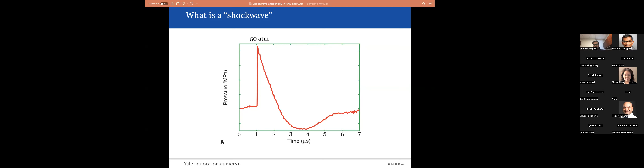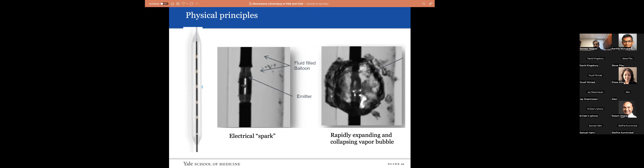So there's a transfer of electrical energy from a generator that's hooked up to the balloon catheter via an electrical cord, and that electrical spark ignites an emitter that is inside the fluid-filled balloon with 50-50 saline and contrast, and that induces the formation of a rapidly expanding and collapsing vapor bubble. And this initiates the transfer of an acoustic or sonic pressure wave. So it's not one particle per se that's physically moving continuously in space and then releasing that energy in the calcified lesion. It's actually a wave or a transfer of mechanical energy by moving neighbor particles and then returning each particle to the base equilibrium state. So it's basically an ultrasonic pressure wave.